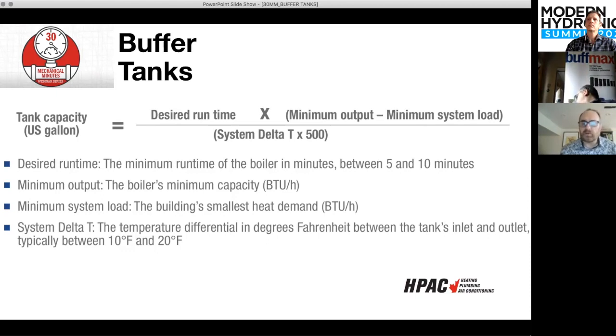Two components that I don't mind oversizing are buffer tanks and expansion tanks, which we won't talk about today. But a buffer tank, in my mind, you can never be too big. Bigger is better when it comes to a buffer tank, but you do have to measure that against cost. I've got to balance the biggest one I can get for my money and the space allowed. So how do we size it?